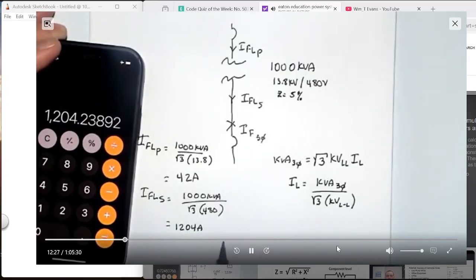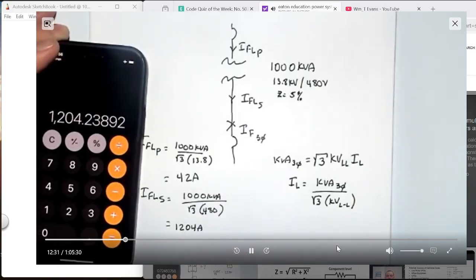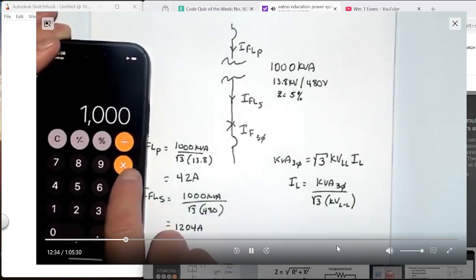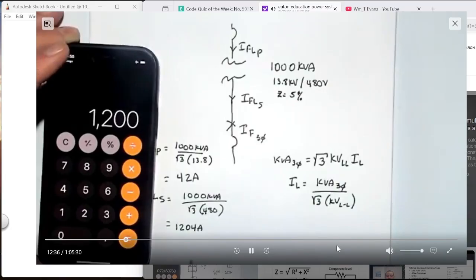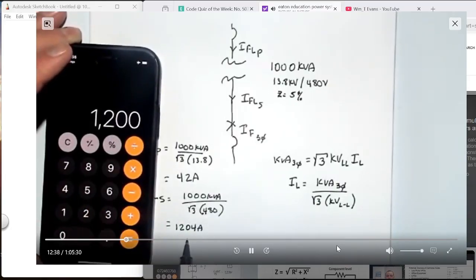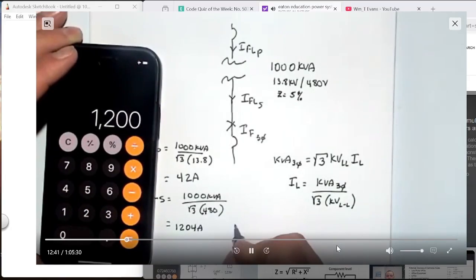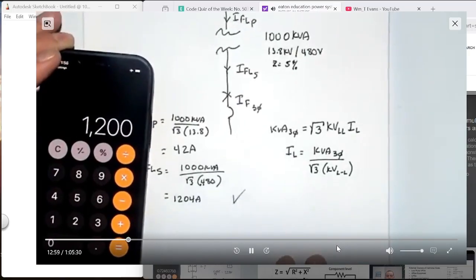One really cool thing about 480 volt systems is that if you take 1000 kVA, multiply it by 1.2, guess what? 1200 amps, 1204. So there's a good rule of thumb that says if you have full load amps on a 480 volt system, it's about 1.2 times the kVA rating of the transformer. Now, let's take this to the next step, which is how do I calculate my fault current?